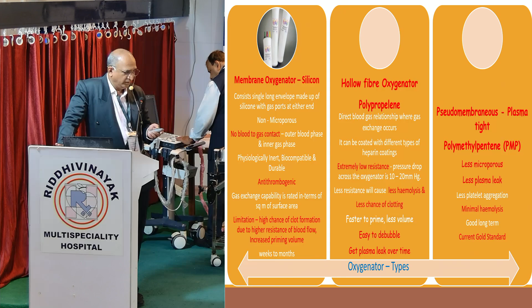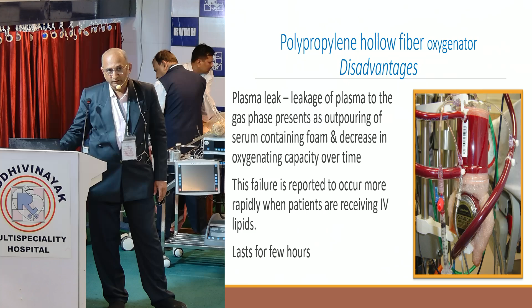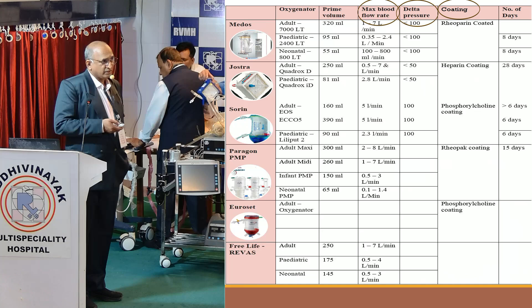This is what happens when you see a polypropylene oxygenator. Can you see this? You can start seeing the plasma leak from the oxygenator, and that occurs after 4 to 6 hours of using it. So that is the polypropylene oxygenator. The gold standard is now the PMP oxygenator. There are different types of PMP oxygenator available now.